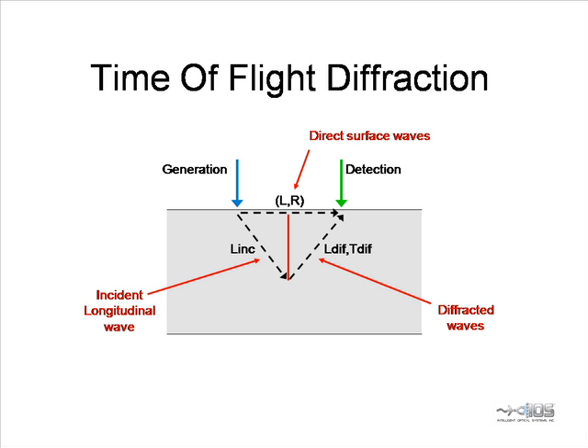For measuring the crack depth, we use the familiar time-of-flight diffraction technique, in which we detect a wave that travels to the crack tip and then diffracts up to the surface on the opposite side of the crack. The time-of-flight and wave velocity can be used to determine the propagation distance. The crack depth is determined from this value and the known beam separation on the surface.